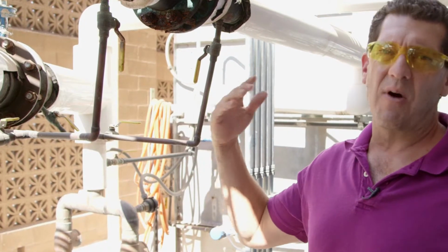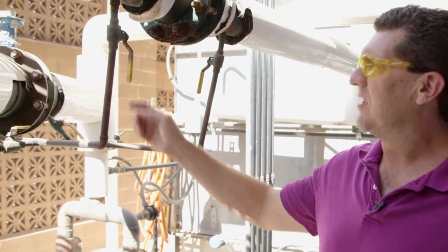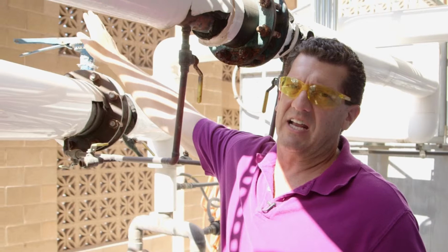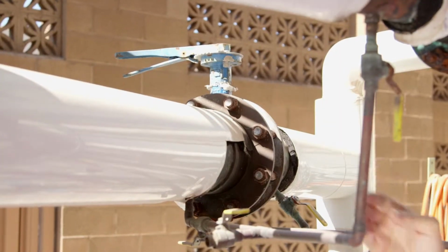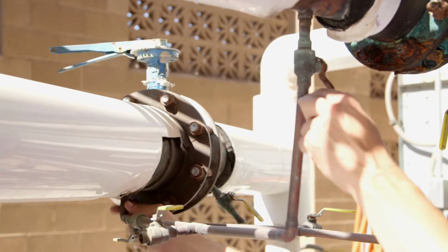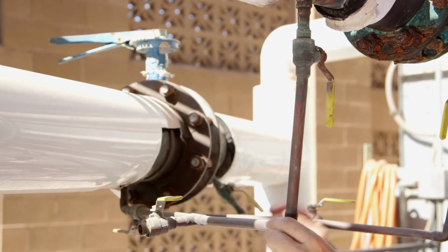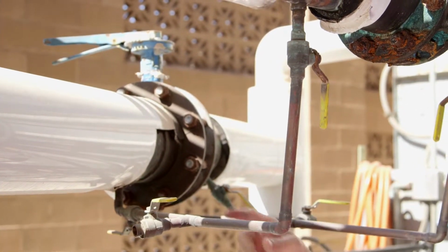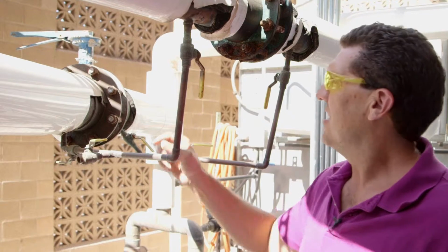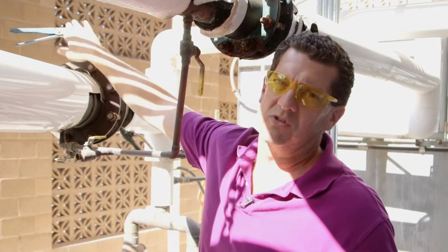This can either be up on the roof or in this case down on the ground. This is the crossover valve right here. And luckily on this system, because they've had an issue in the past, you can see what they've done so that valve doesn't have to be exercised. If something like this isn't in place, then each service we should open and close this.